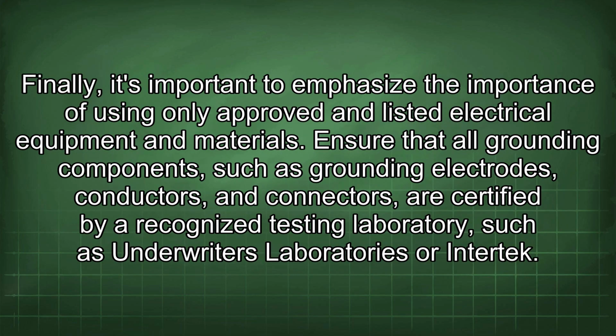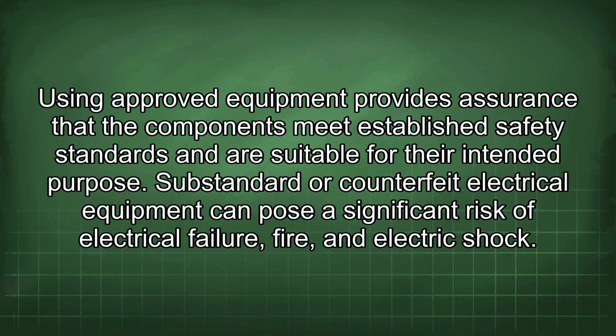Finally, it's important to emphasize the importance of using only approved and listed electrical equipment and materials. Ensure that all grounding components such as grounding electrodes, conductors, and connectors are certified by a recognized testing laboratory such as Underwriters Laboratories or Intertek. Using approved equipment provides assurance that the components meet established safety standards and are suitable for their intended purpose. Substandard or counterfeit electrical equipment can pose a significant risk of electrical failure, fire, and electric shock.